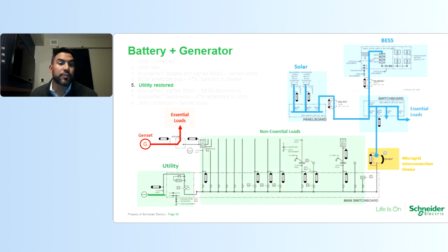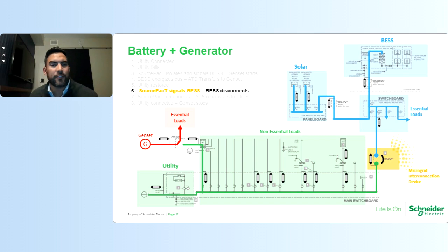Now, when utility is restored, the ATS will detect that utility is available. Both the ATS and the microgrid interconnection device have a 60-minute retransfer delay. So you can program that device to allow up to 60 minutes before we transfer back to the utility source. That can be programmable as well. It can be 1 minute, 2 minutes, 5 minutes, depending on how utility responds. As utility is restored, SourcePacT will signal to the energy storage system, after a time delay, to change state from grid forming to grid tied.